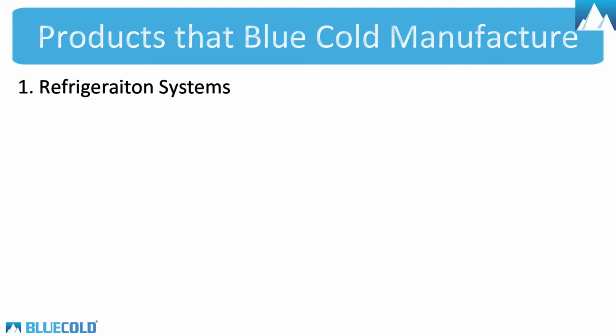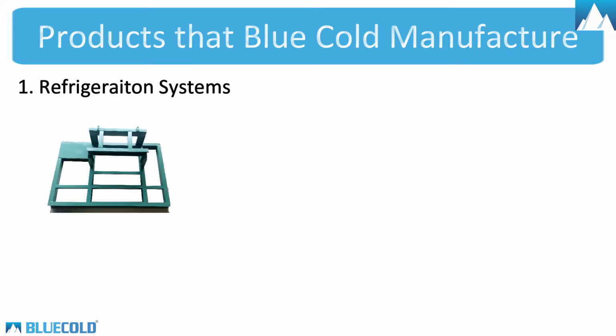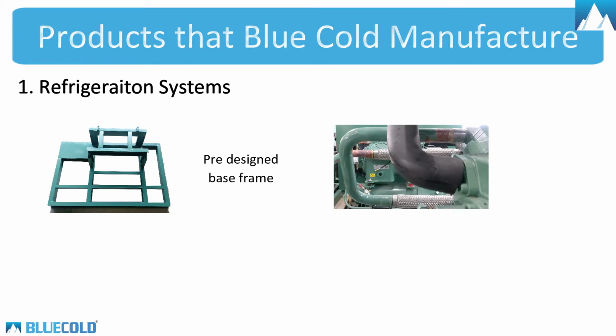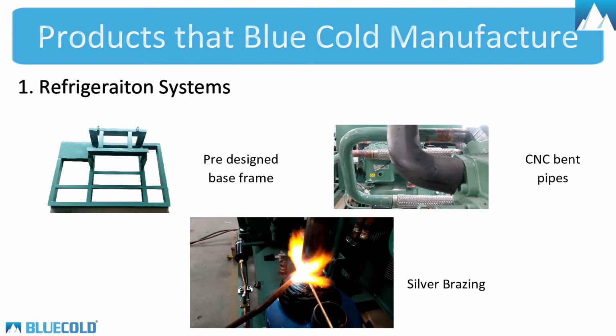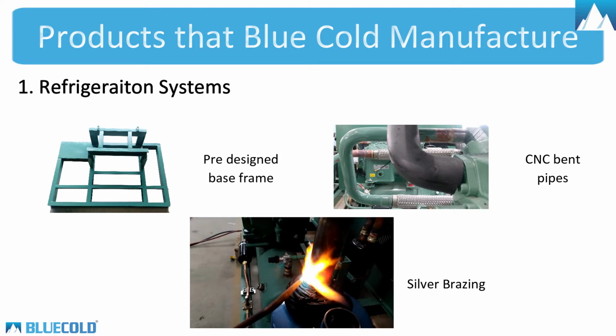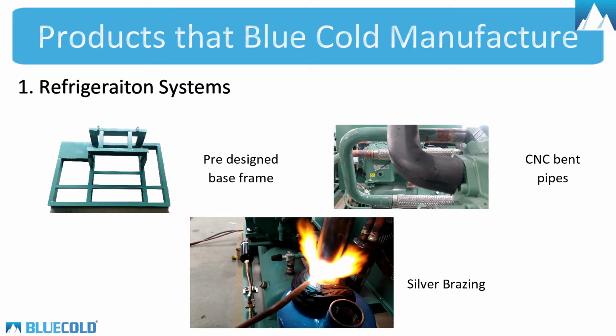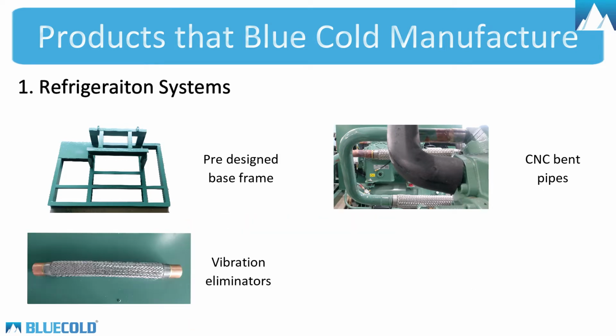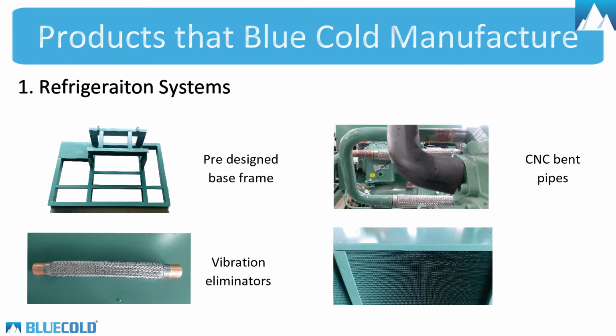All the components are mounted on a pre-designed base frame for every individual model. We use CNC bent pipes in our outdoor units to reduce the risk of leakages in the bending portion with silver brazing, which is brazed under an inert nitrogen atmosphere at the joints. Vibration eliminators on the pipes, which have the maximum impact of vibration during the operation of the system. Powder-coated air-cooled condenser to give a long-lasting performance.